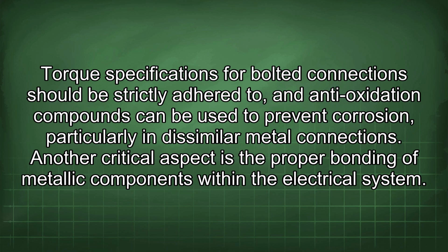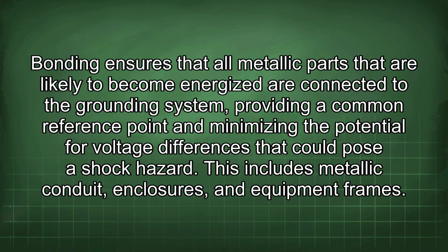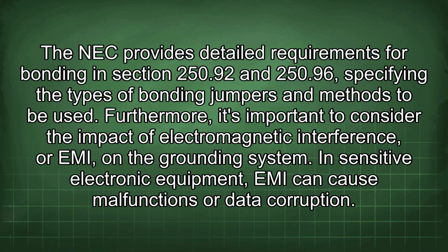in dissimilar metal connections. Another critical aspect is the proper bonding of metallic components within the electrical system. Bonding ensures that all metallic parts that are likely to become energized are connected to the grounding system, providing a common reference point and minimizing the potential for voltage differences that could pose a shock hazard. This includes metallic conduit, enclosures, and equipment frames. The NEC provides detailed requirements for bonding in Section 250.92 and 250.96, specifying the types of bonding jumpers and methods to be used.